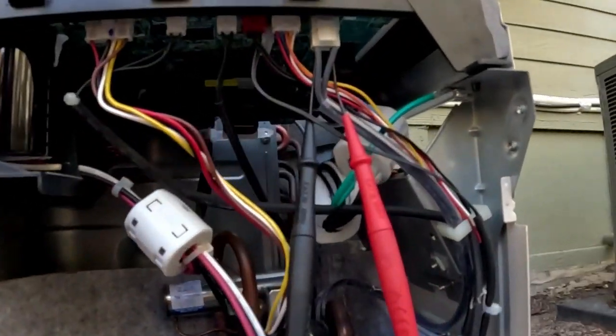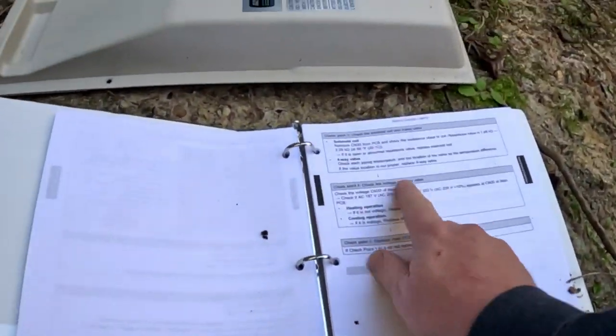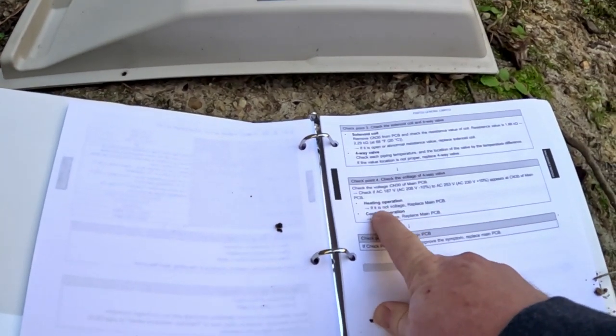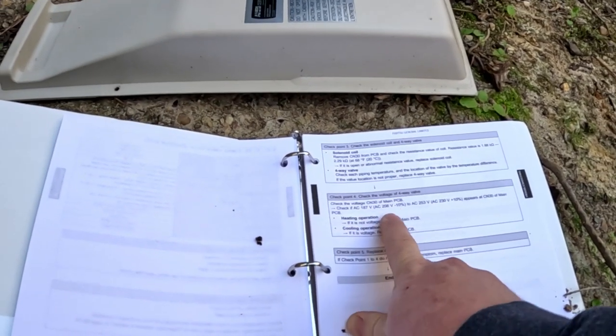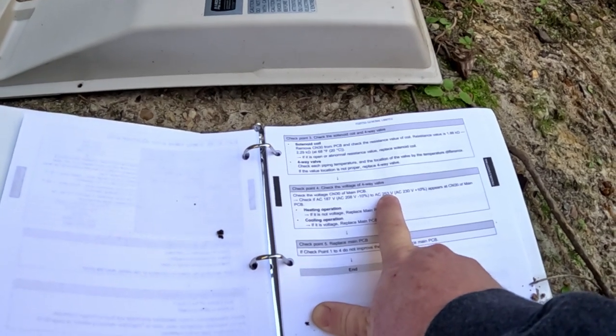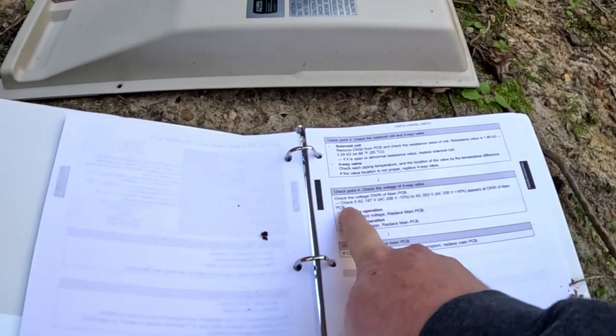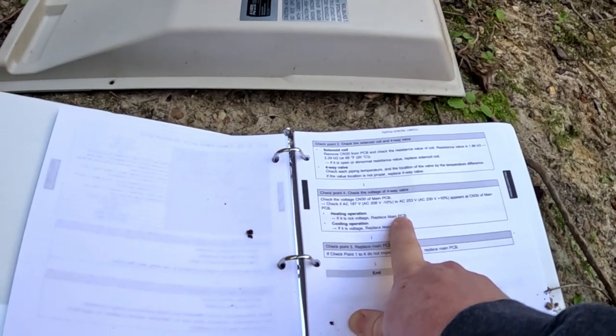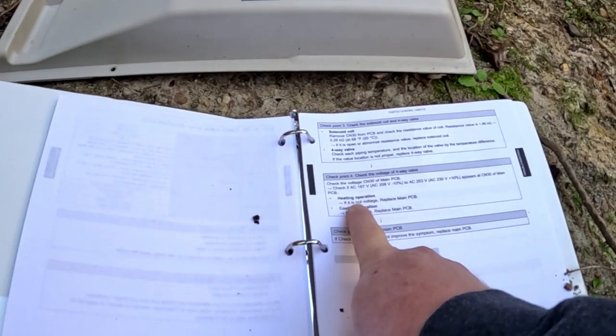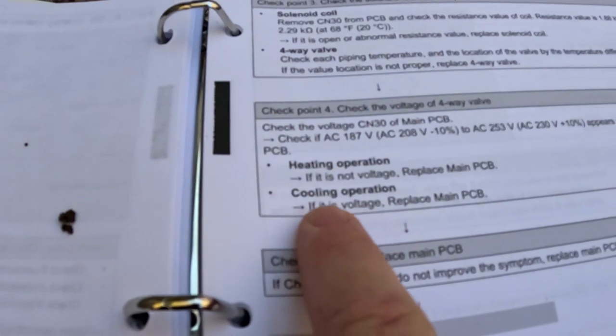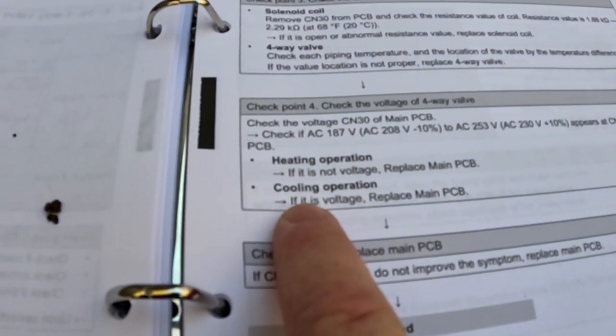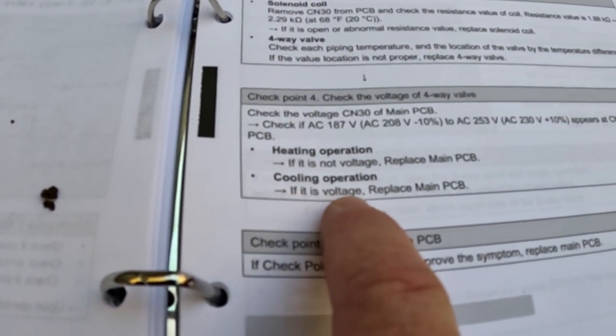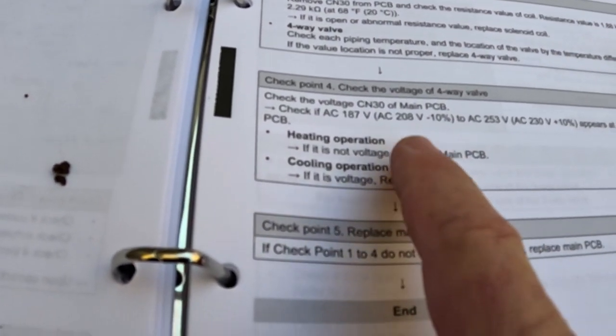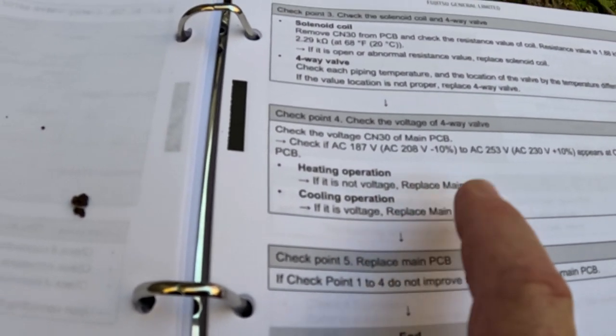All right guys, one thing I'm going to try real quick. I'm going to plug this thing back in. I've got my needle leads back up inside that plug. So according to this, in heating operation, if you do not have your high voltage on this terminal where that thing's plugged to, replace the board. So evidently this thing energizes in heat mode, and in cooling operation, if there is voltage, replace it. So evidently this thing energizes in heating and not cooling.